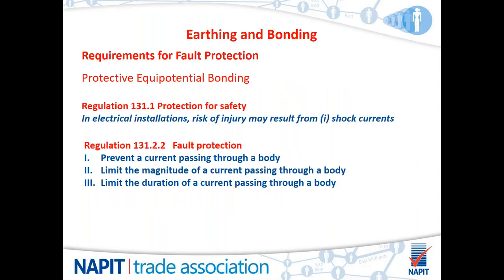Again, a requirement for fault protection. In electrical installations, the risk of injury may result from shock currents. One of the fundamental principles of the regulations is to make sure that shock currents do not result in somebody's injury. And the way that is done is to prevent the current passing through the body totally, to limit the magnitude of that current passing through the body, and then also to limit the duration of the current passing through the body, obviously done by making sure that the protective device operates within a required time.